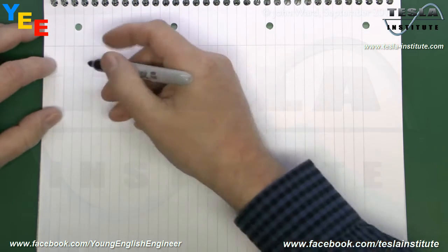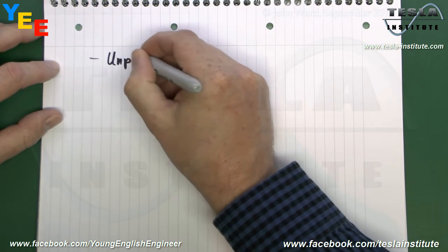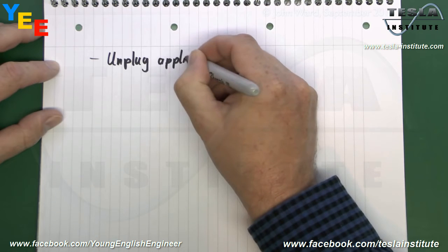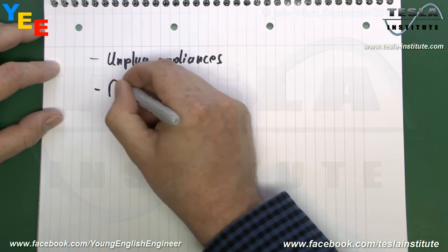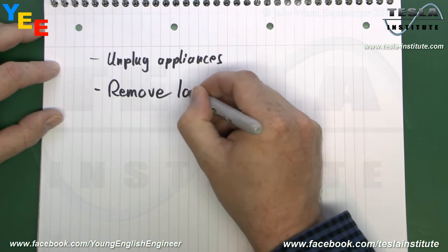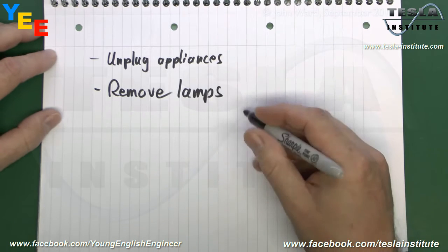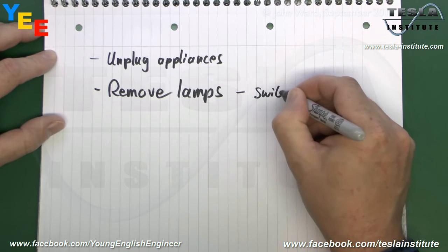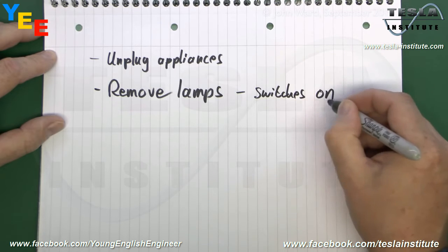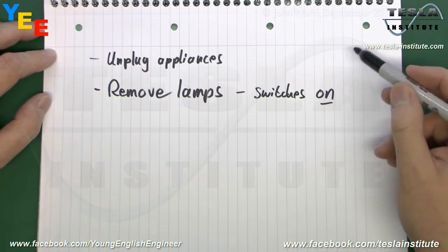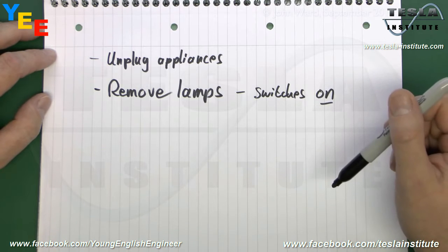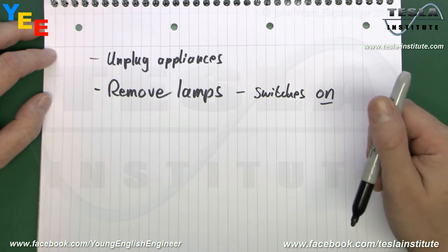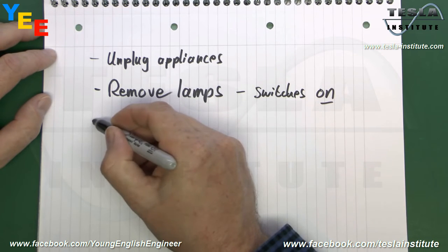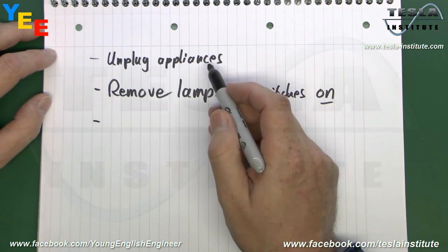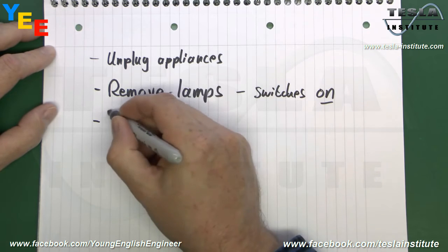So on an existing circuit, first of all you need to unplug any appliances that are connected there. Remove lamps, if it's a lighting circuit, and you also need to make sure that the switches for the lights are actually in the on position, because otherwise you're only going to be testing part of the circuit, and if there was a fault on the actual cable to a switch, if the switch was in the off position, that fault may not actually show up. And other things to be aware of, as well as unplugging things, you may have items connected permanently either via isolators or fused connection units, so you do need to switch those off as well, particularly in the kitchen.